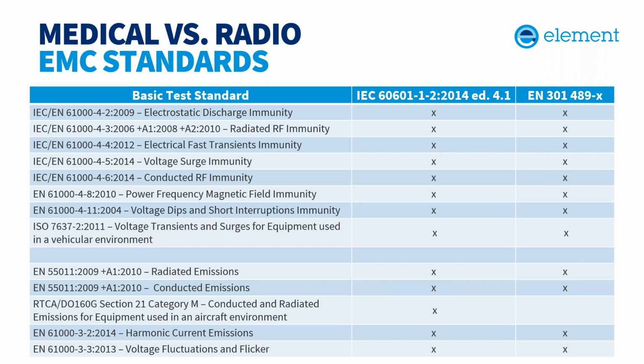Another thing to note is that limits may be different between the standards. -1-2 only requires emissions above 1 gigahertz for group 2 devices, but with 301 489, since you're including a radio, if there's a clock greater than 108 megahertz or a signal internal to the product greater than 108 megahertz, say a Bluetooth radio or Wi-Fi radio, emissions testing needs to go above 1 gigahertz. So you need to make sure that you're meeting all the limits required for a product.